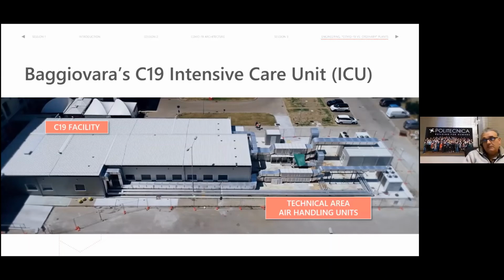However, one very important thing is that you can use it for COVID-19 under negative pressure. You can use it for a normal intensive care unit with over pressure, but you cannot use it for both together. So you must decide if you want to move to the other mode of operation. Then you have to clean up everything, disinfect everything, and then you can go in the other mode of operation and stay there. It is not so easy to move from one mode to the other very quickly, even because this is a unique room.